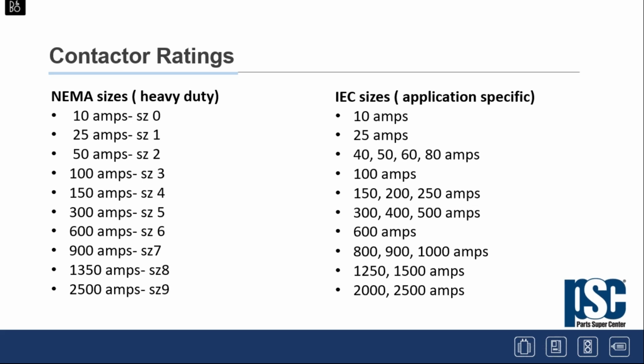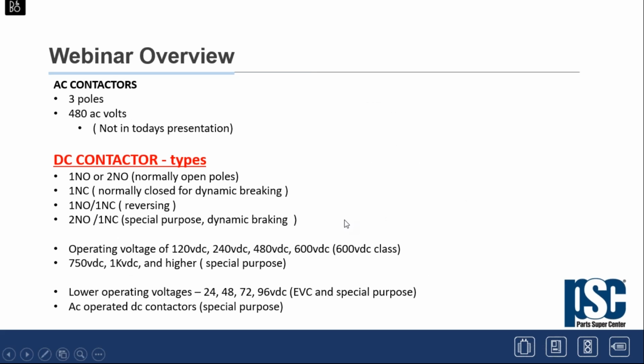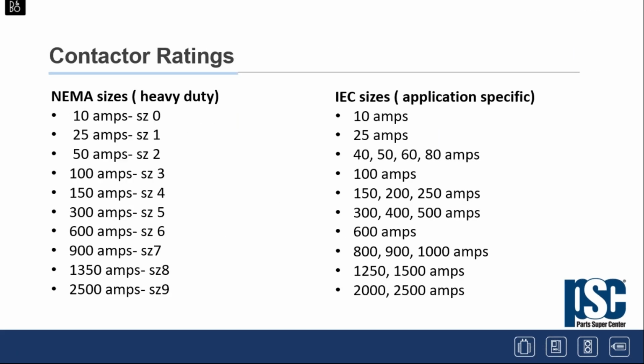Okay, when we talk about contactor ratings, and these apply specifically to DC that we're talking about today, but are also applicable for AC, we have the NEMA rating. To give you a little background, NEMA, National Electrical Manufacturers Association, established these ratings back in the 1950s. And basically the NEMA devices I would call heavy duty application, very general. They run in current ratings from 10 amps, which would be a size 0, up through 2500 amps, which is size 9. And again, AC and DC also have these same kind of ratings.